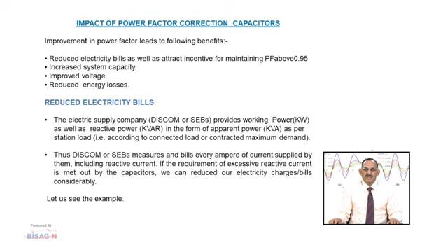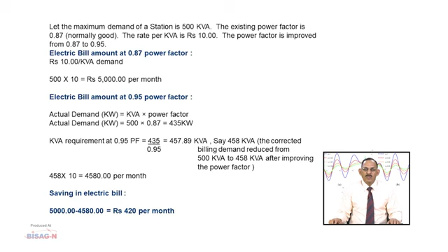The electric bill amount at 0.87 power factor is rupees 10 per kVA demand, so 500 into 10 equals rupees 5000 per month. Electric bill amount at 0.95 power factor: actual demand in kilowatt equals 500 into 0.87, that is 435 kilowatt. kVA requirement at 0.95 power factor comes to 435 divided by 0.95 equals 457.89 kVA, say 458 kVA. The corrected billing demand is reduced from 500 kVA to 458 kVA after improving the power factor. Now, the bill at 0.95 power factor is 458 into 10, that is 4580 per month. Saving in electric bill is rupees 5000 minus rupees 4580 equals rupees 420 per month.